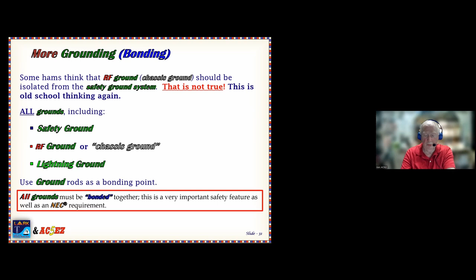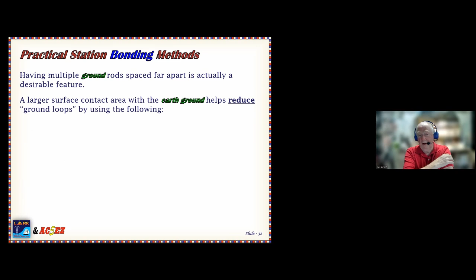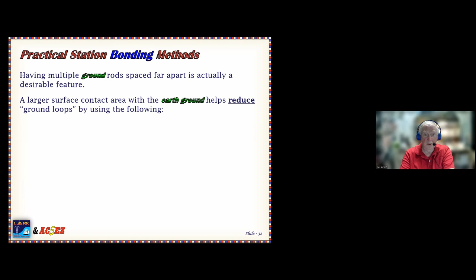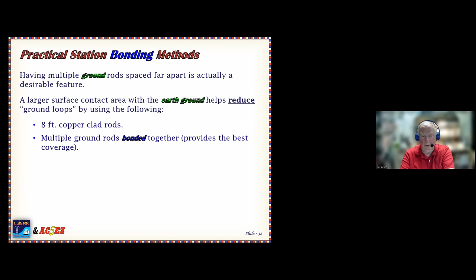Okay, let's look at some practical stations that have multiple ground rods spaced far apart is actually a desirable feature. Remember if you've ever decided, well, I need to put 5 or 6 ground rods in the ground, or I need to put one ground rod, or would one ground rod serve for everything? Well, the large surface area or the large surface contact area with the earth helps reduce ground loops. Now, 8-foot copper rods, multiple ground rods bonded together provide the best coverage, and I'll show you why.